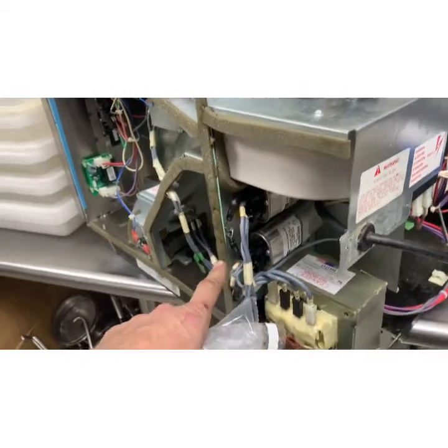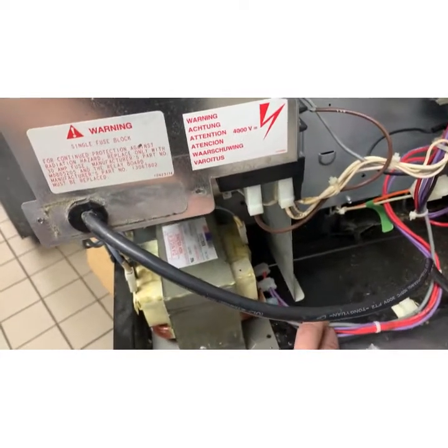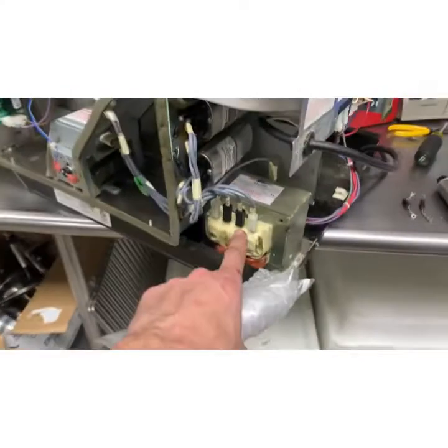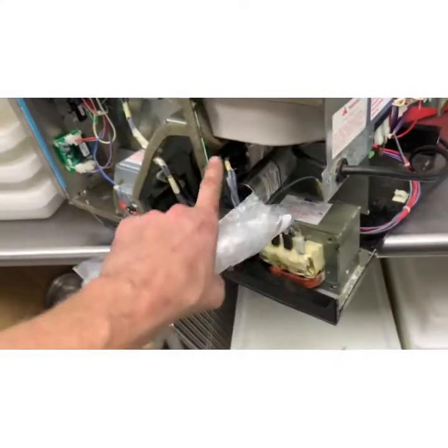I called tech support and they very adamantly told me once I have 208 coming into here, replace everything else on the high voltage side from that transformer forward. Replace the transformer, replace the capacitors, replace the diodes, replace the magnetrons.